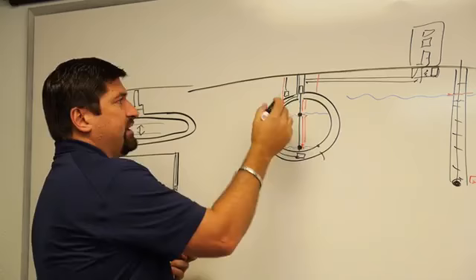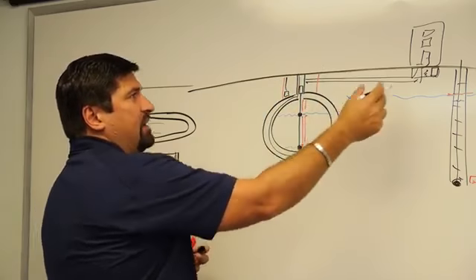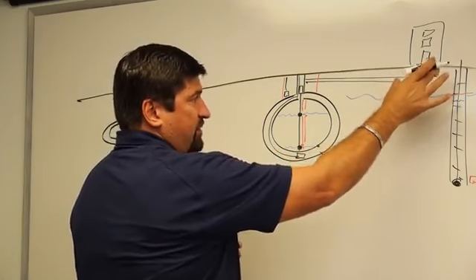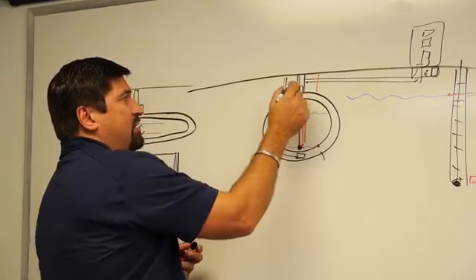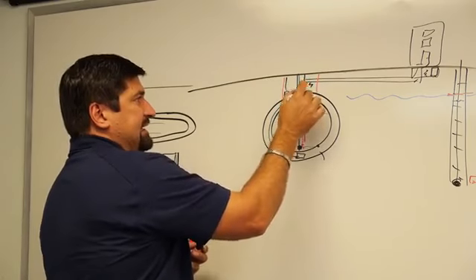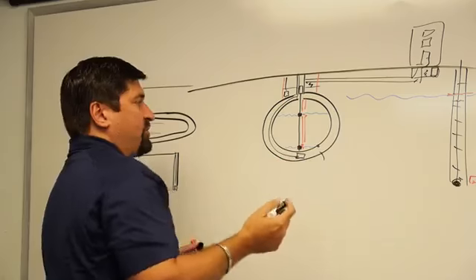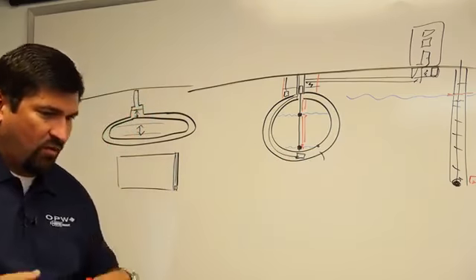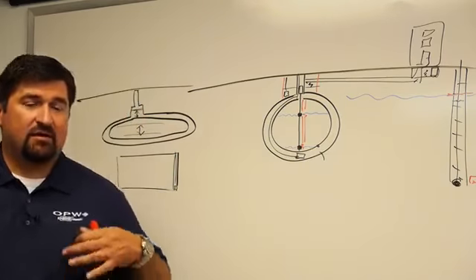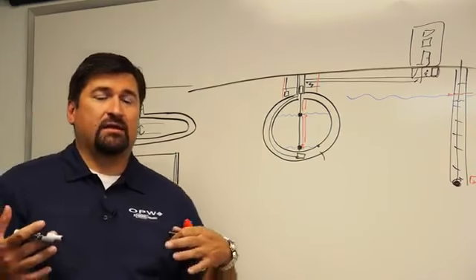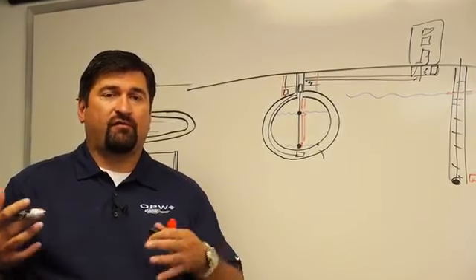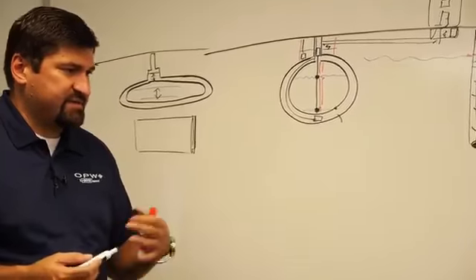I'm just basically putting a sensor in this STP sump, same as I would put it in a dispenser sump or a dispenser pan, and it's just monitoring to make sure that this piping isn't leaking in here, filling this up with product or with water. Now, one of the things that you look at is, is there a way to distinguish between just regular water or fuel? Well, there's multiple types of sensors.